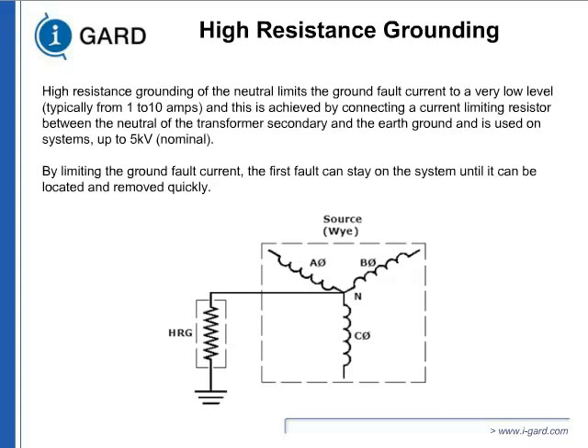Why were solid grounded systems not popular? Because on the first fault, there will be such high current, it can do a tremendous amount of damage, and you shut down. So this was the best of both worlds. You can limit the ground fault. That means on the first ground fault, you can continue operation, and it's technically grounded. So technically you limit the overvoltages and you have flexibility to locate. Then the next slide will show you how we came up with detection schemes.